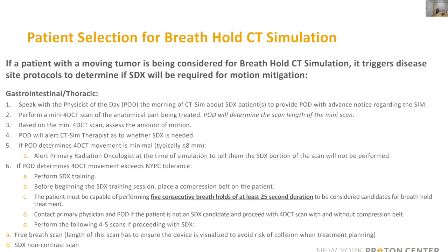If the motion on that 4D scan, and generally this 4D CT scan is being done with compression belts in place already, is less than 8 millimeters, we at that time will determine that that patient does not need the SDX component for their treatments, in part because we feel less than 8 millimeters is relatively minimal motion that doesn't necessarily require the slight increased time that's necessary for treatment delivery with breath hold.